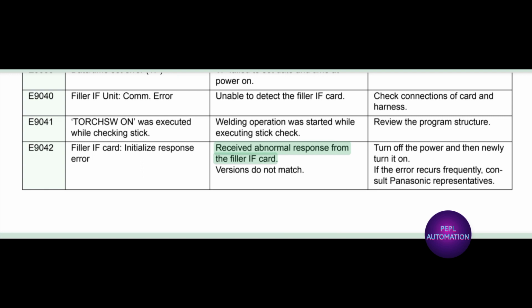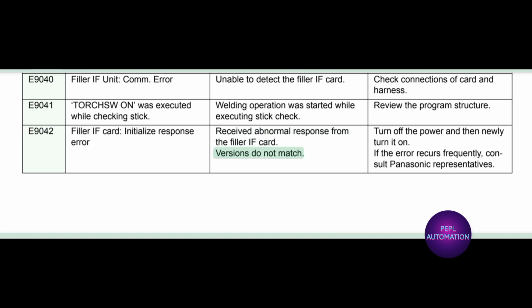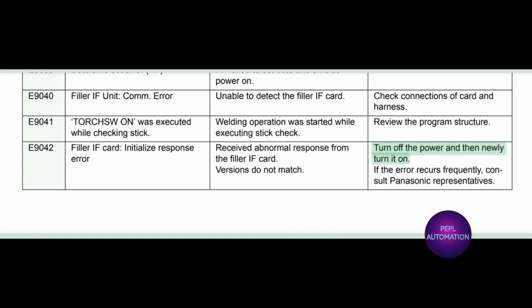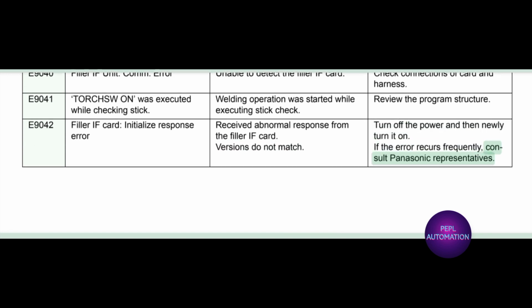E9042, filler IF card, initialize response error. Received abnormal response from the filler IF card. Versions do not match. Turn off the power and then newly turn it on. If the error occurs frequently, consult Panasonic representatives.